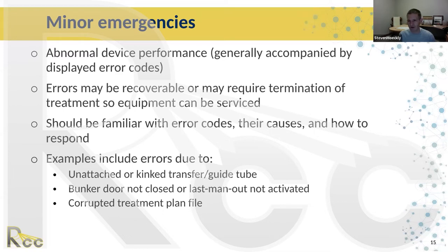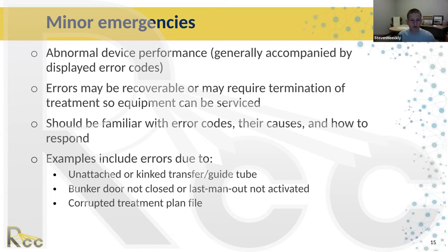Minor emergencies include abnormal device performance or error codes — these may be recoverable with a computer restart, or may require service. You need to be familiar with the error codes; your vendor should provide manuals. If buying from a third party, contact the vendor for manuals or reach out to someone with the same unit. Minor alarms can include errors from kinked transfer tubes, guide tubes that are unattached, the bunker door not being closed, or the last man out switch not being activated.